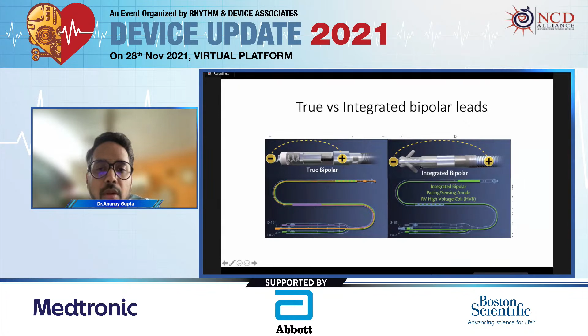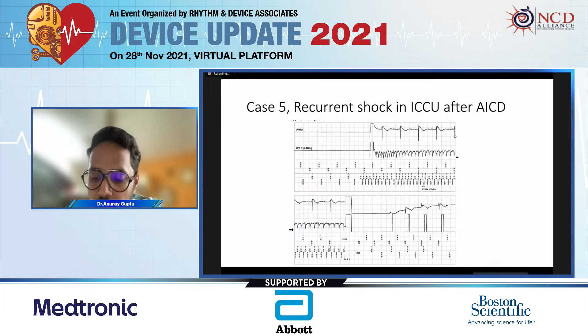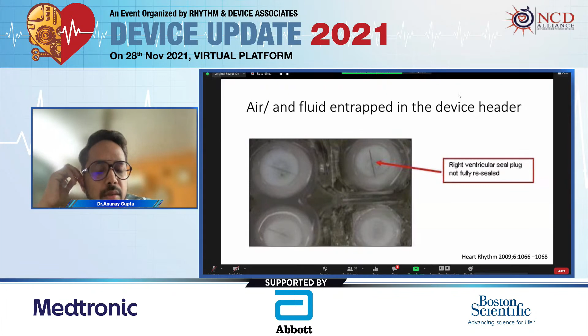A patient receives a shock immediately after ICD implantation in the ICU. You can see there are multiple high frequency signals on the RV tip and RV ring, and the duration is decreasing over time when the patient receives a shock. If it happens immediately after the implantation, the most common cause is air in the header. So what happens if we don't remove the air properly while inserting the device lead tip? Air can get entrapped, and over time it gets released and leads to interference between the signals, causing a high frequency signal and inappropriate shock. Nothing has to be done for this. Within 48 hours this air gets released, and you can just turn off the therapy in the ICD, and within 48 hours the air will get released. Nothing to be done for that.